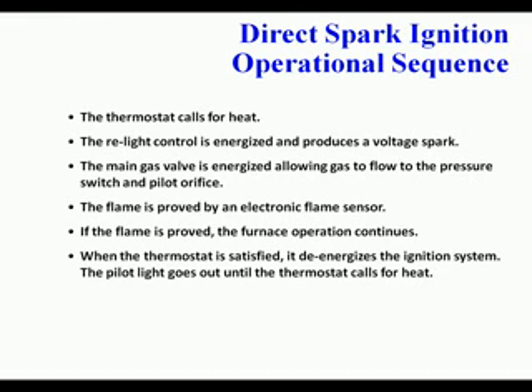On a direct spark ignition system, the thermostat calls for heat, the re-light control is energized and produces a voltage spark. The main gas valve is energized, allowing gas to flow to the pressure switch and pilot orifice. The flame is proven by an electronic flame sensor. If the flame is proved, the furnace continues operating. When the thermostat is satisfied, it de-energizes the ignition system. The pilot goes out until the next thermostat call for heat. Again, you have flow charts available in most operation manuals and service procedures. Make sure you use them.